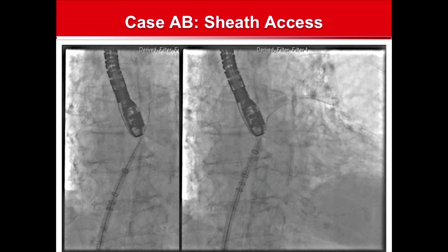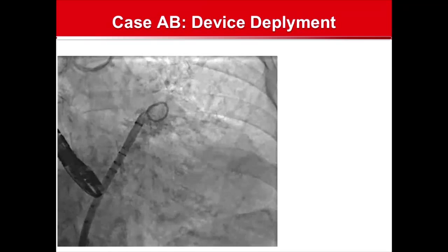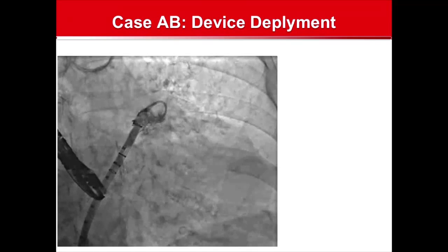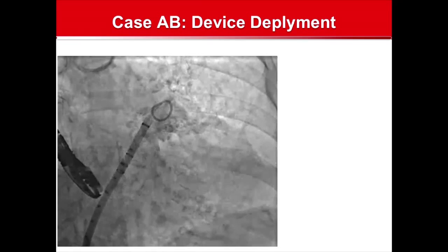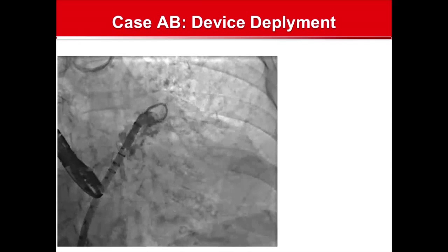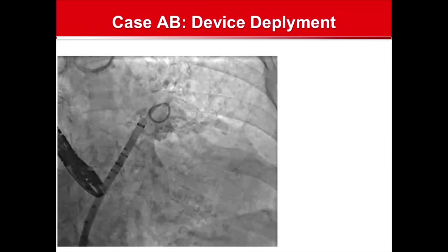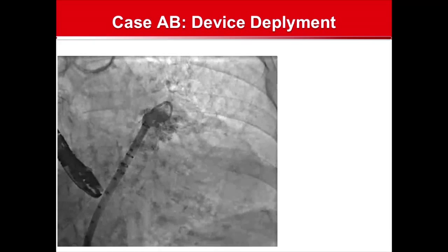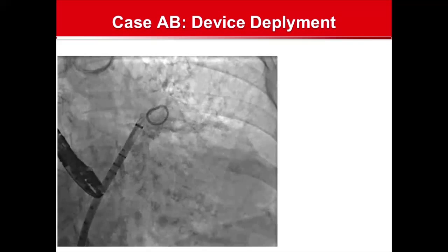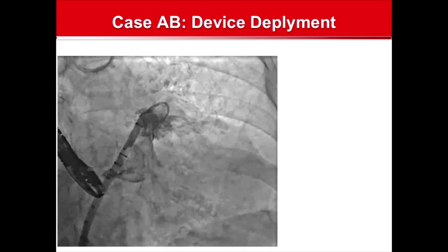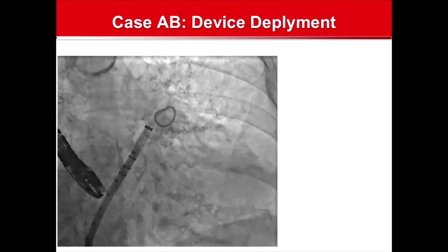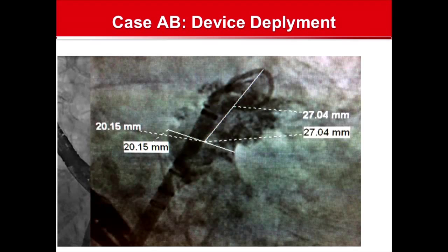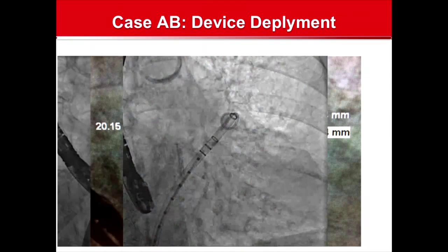Once we have positioned the sheath across the septum, we use a pigtail to gently navigate our system into the left atrial appendage. And here's an example where we've taken a cine angiogram with a marker pigtail, and you can see the structure here. This atrial appendage is quite similar to what we've seen on the baseline CT images. So we would obtain fluoroscopic measurements. In this case, you can see the orifice was measured at about 20 millimeters, and quite similar to what we obtained on CT. So we selected a 24 millimeter device.